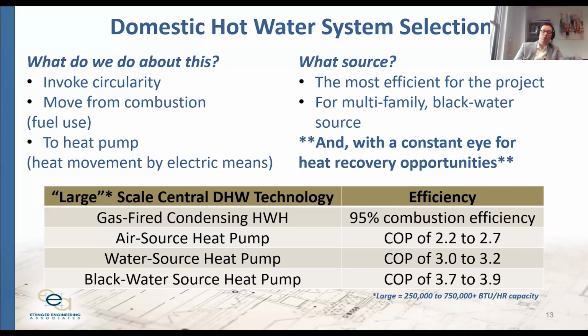So what source am I asking this heat pump to use? Air source is one, but the problem is that the coefficient of performance, or efficiency, is relatively low. COP is the ratio of energy out versus energy in. So if an air source heat pump has a COP of 2.5, for every watt of electricity I send to the unit, I get 2.5 units out just from moving energy. That's good — 1 for 2.5 is good.